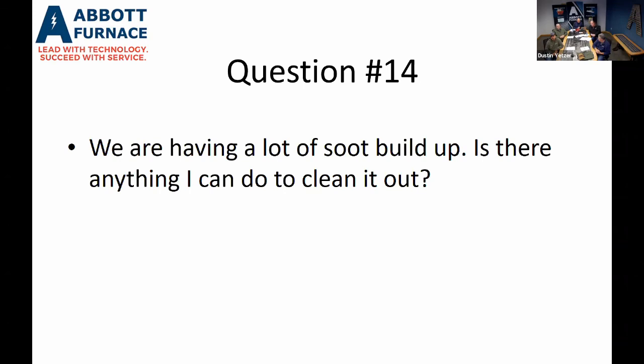But basically it's removing all the atmosphere out of the furnace, so it's just air inside. And this is done in a very controlled manner, introducing outside air, oxygen, into the furnace at an elevated temperature that will essentially burn that material up. Now, if this is the first time you're doing this and there's a lot of buildup, there's smoke going to come out of everywhere. So just be cautious, take it slow. But that's one thing that can help.